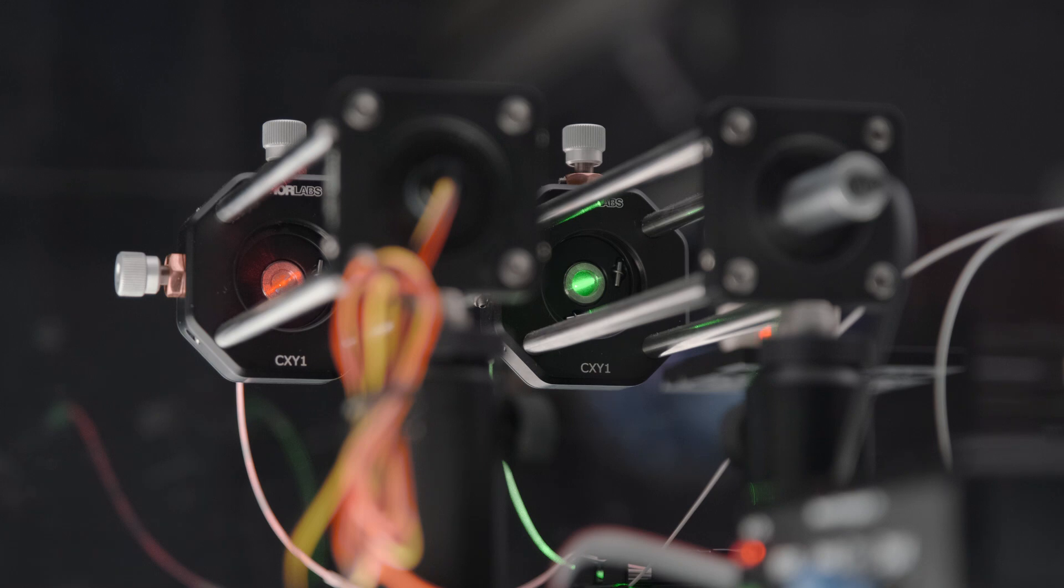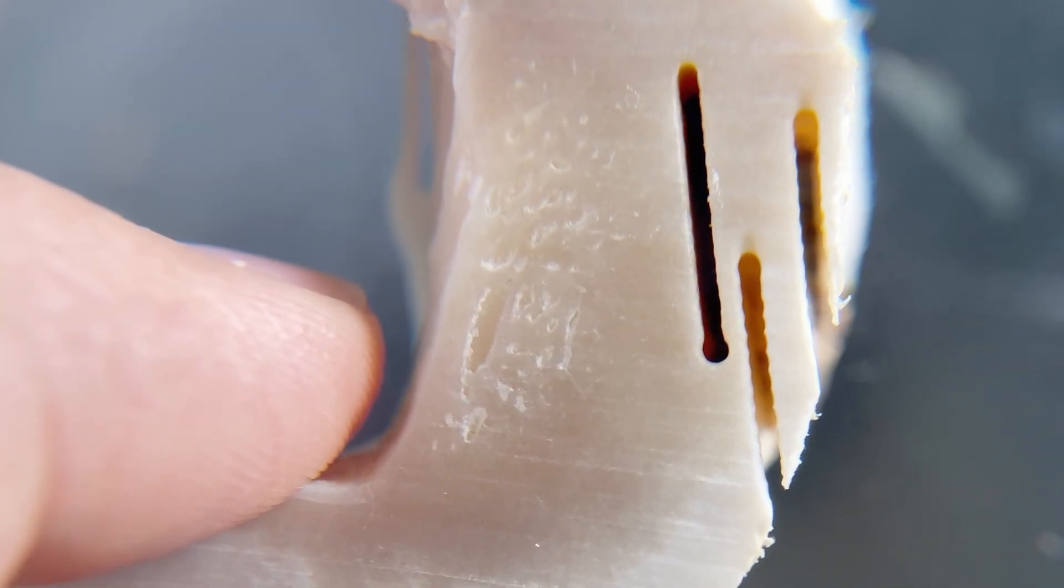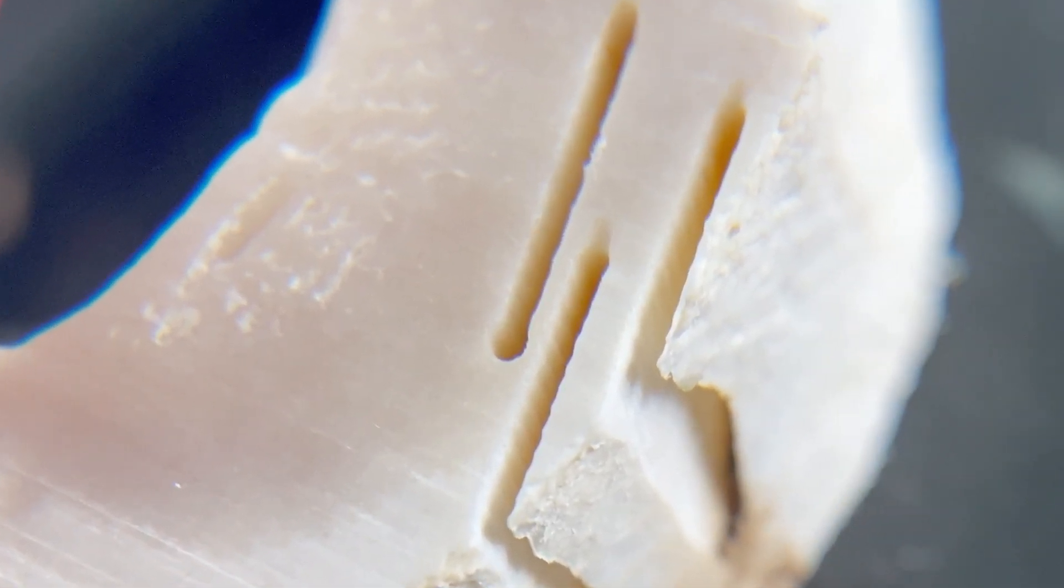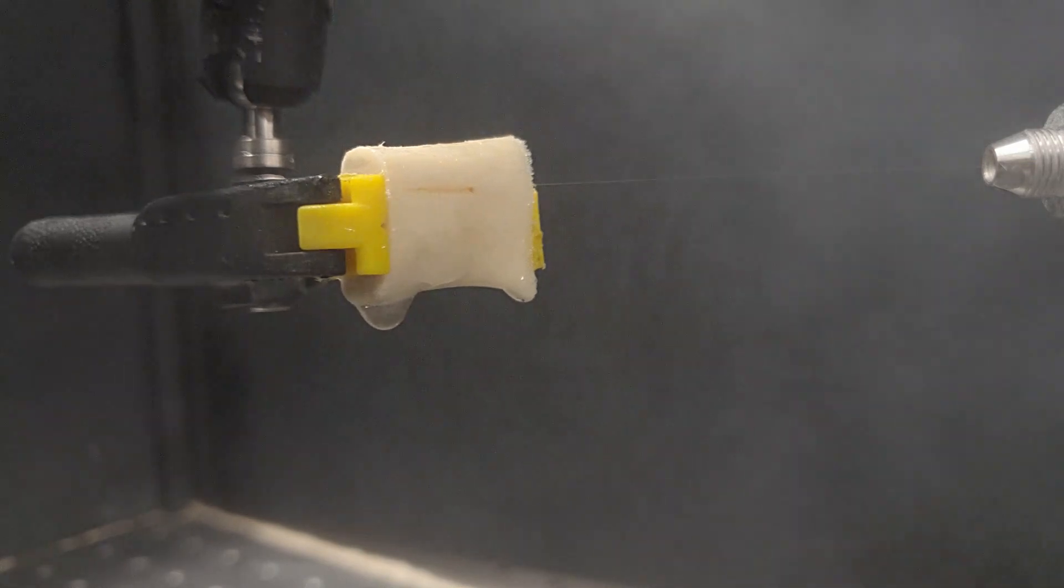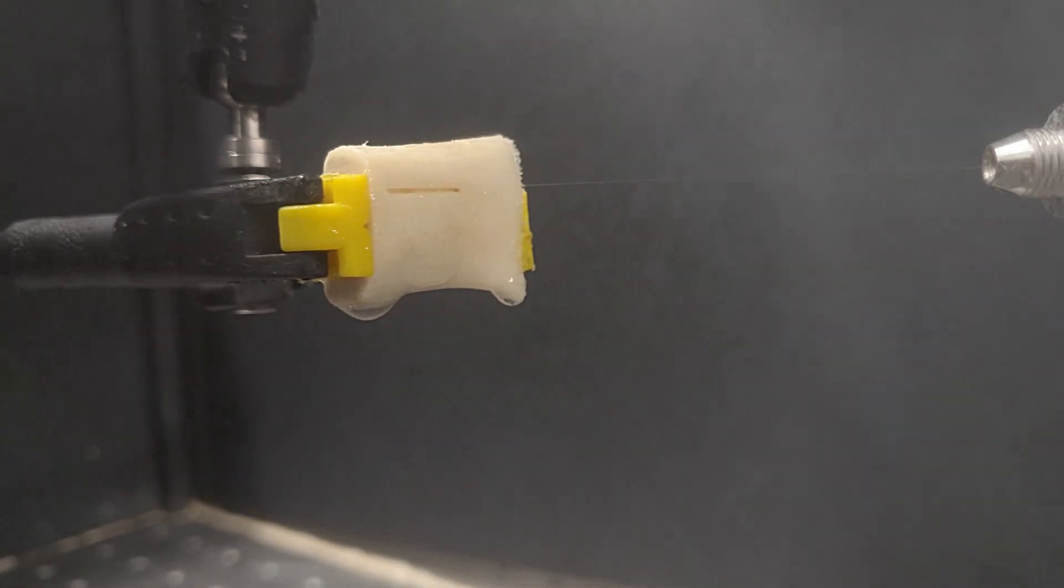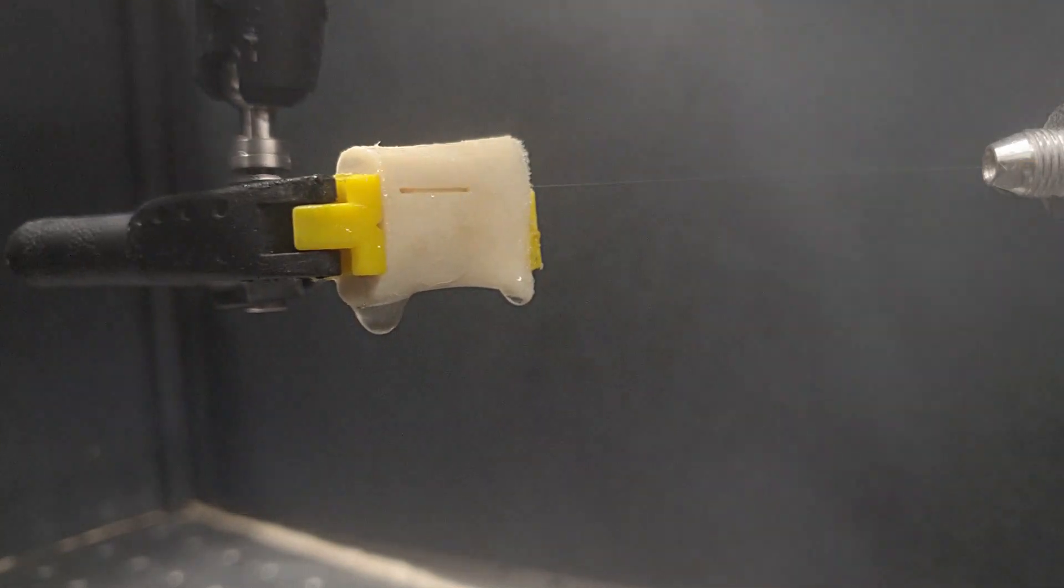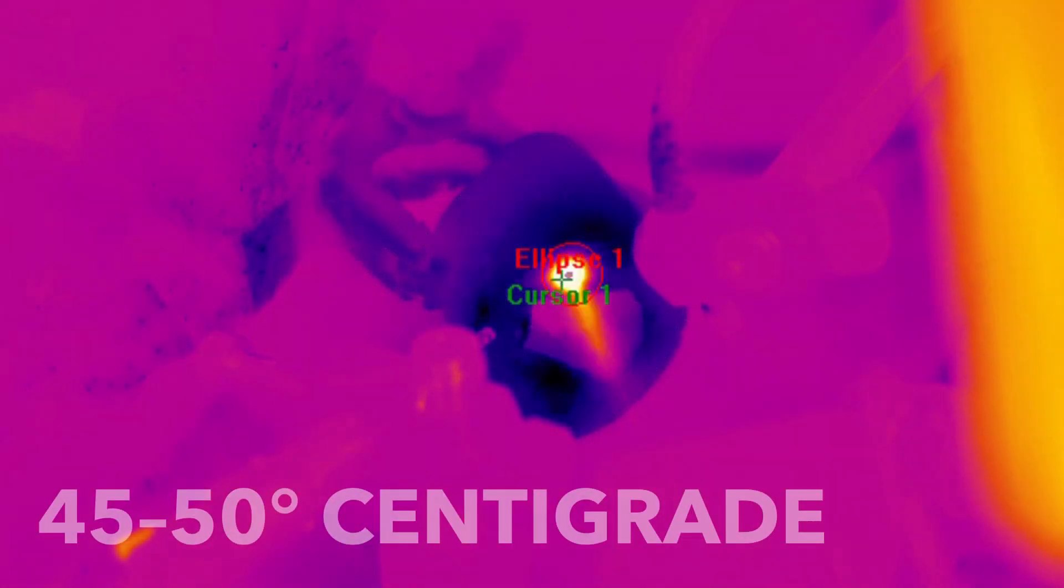Laser physics changed so that we could do these cuts in cold ablation. If you look into the cellular structure of the bone, you have the impression the bone didn't even realize that it was touched. The laser light is only absorbed by the water and not by the bone itself. And then water expands due to vaporization and then chips away the bones. And this is flying out of the cut with a speed of Mach 2. And the remaining tissue stays cool. We never observed temperatures higher than 45, 50 degrees centigrade. This is why the bone and the natural material is still intact.